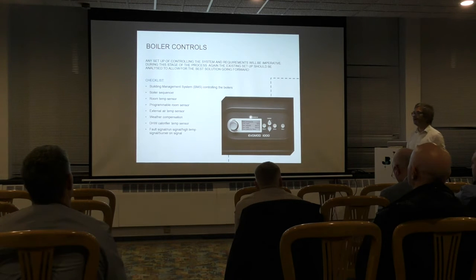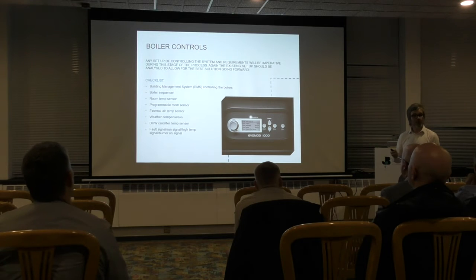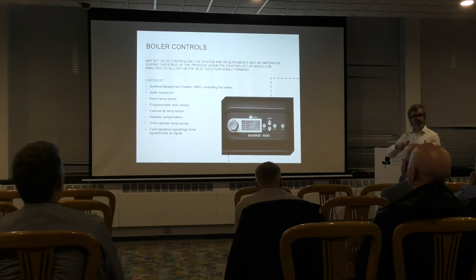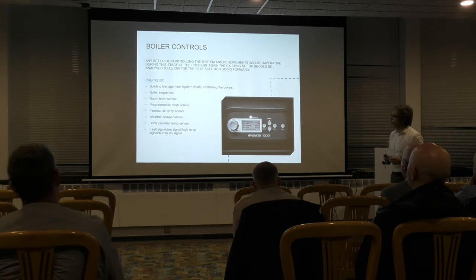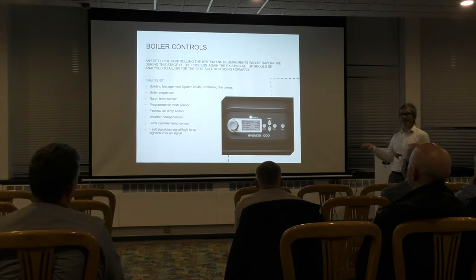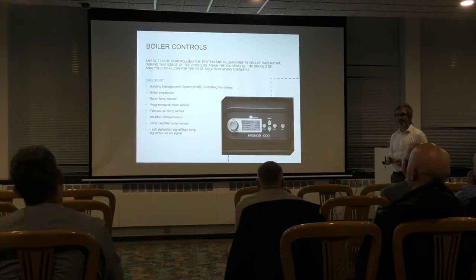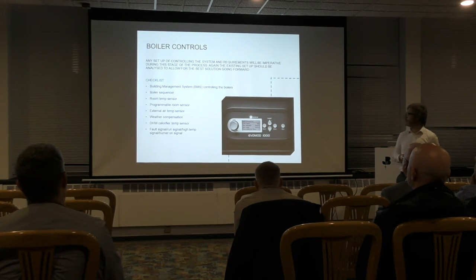But it could be that maybe they don't want to look at that, and they want the boiler manufacturer supplying a full, we can't supply full-blown BMS systems, but we can supply control systems that can do a lot, control other zones and that type of thing, to improve the efficiency of it. So really, do we want to start looking at putting boiler sequencers in? Obviously, if we haven't got BMS and we're putting a bank of boilers in, we'll put sequence controls in. I'll be looking at room temperature sensors, programmable room sensors. If we want weather compensation, obviously we're going to have to put external air temperature sensors in. If we've got a calorifier there, and our boilers are serving that calorifier, then we're going to need a domestic hot water sensor going back to the boilers to accommodate that. And then finally, we put fault signal, run signal, high temperature signal, burner on signal.